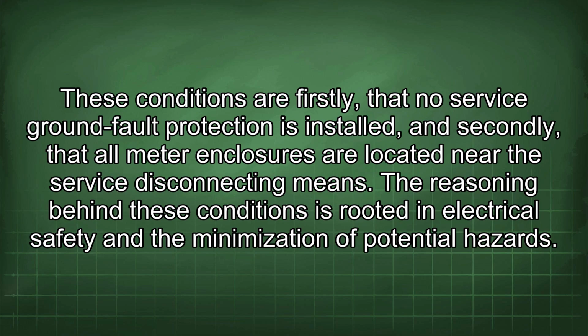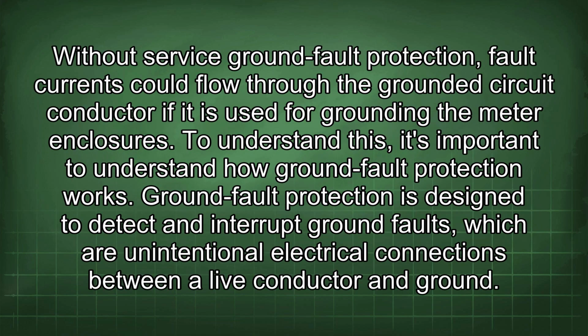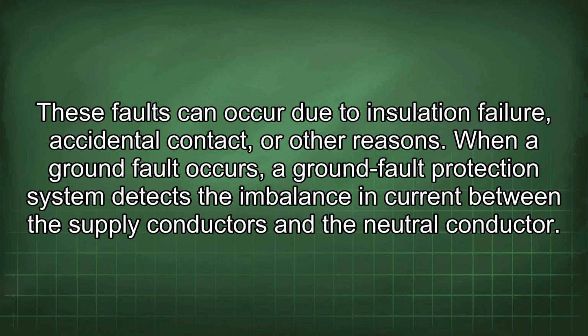The reasoning behind these conditions is rooted in electrical safety and the minimization of potential hazards. Without service ground fault protection, fault currents could flow through the grounded circuit conductor if it is used for grounding the meter enclosures. To understand this, it's important to understand how ground fault protection works. Ground fault protection is designed to detect and interrupt ground faults, which are unintentional electrical connections between a live conductor and ground. These faults can occur due to insulation failure, accidental contact, or other reasons.